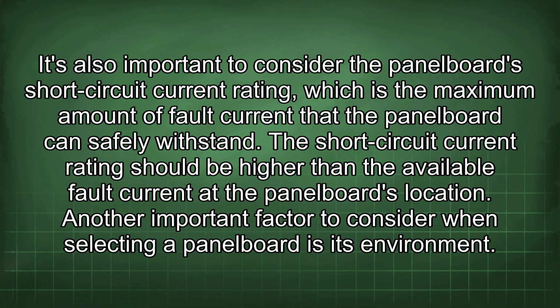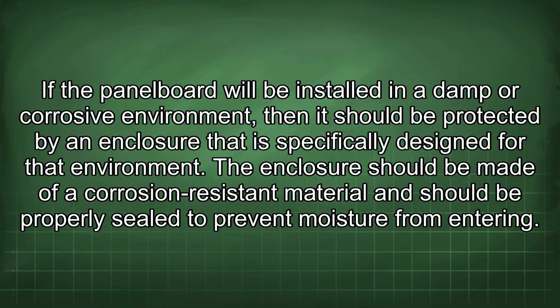Another important factor to consider when selecting a panel board is its environment. If the panel board will be installed in a damp or corrosive environment, then it should be protected by an enclosure that is specifically designed for that environment. The enclosure should be made of a corrosion-resistant material and should be properly sealed to prevent moisture from entering.